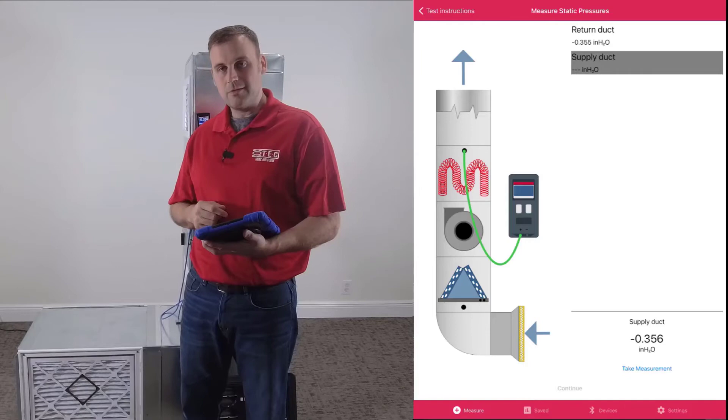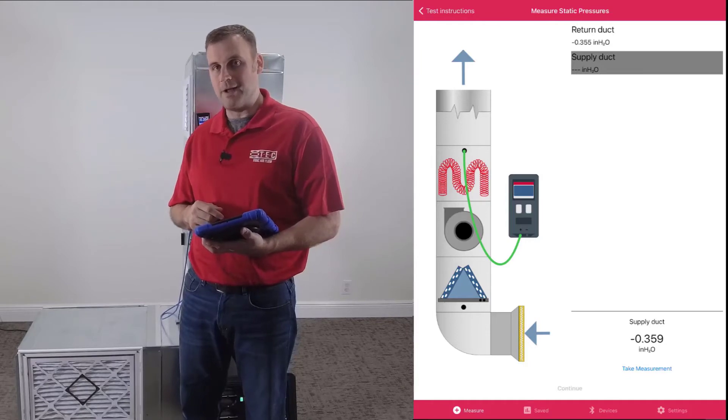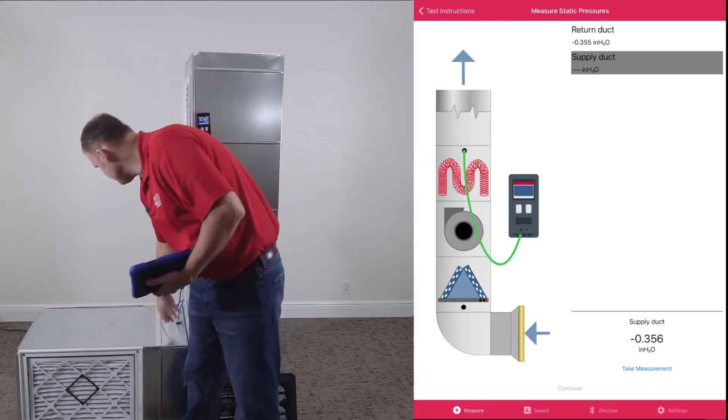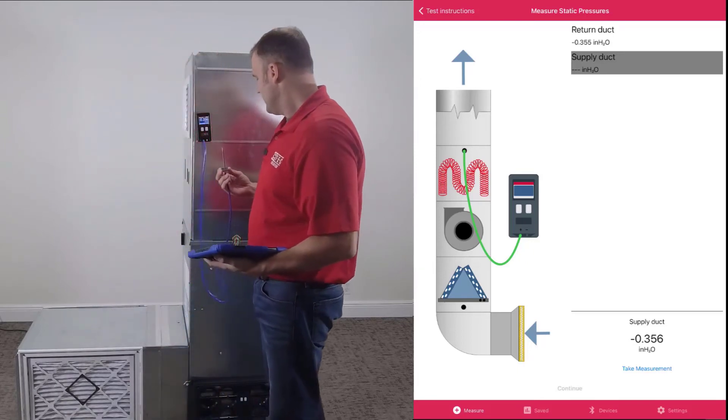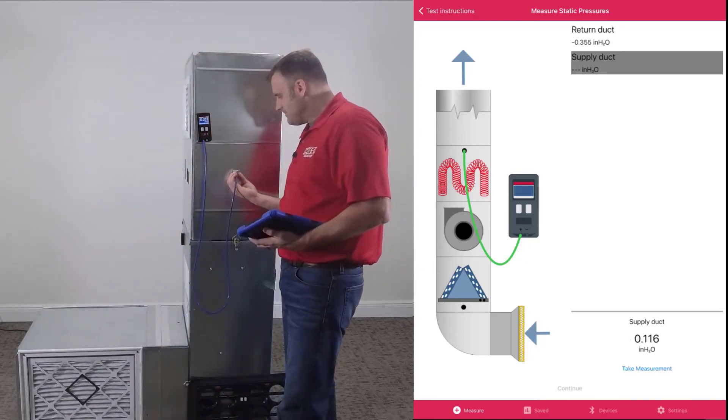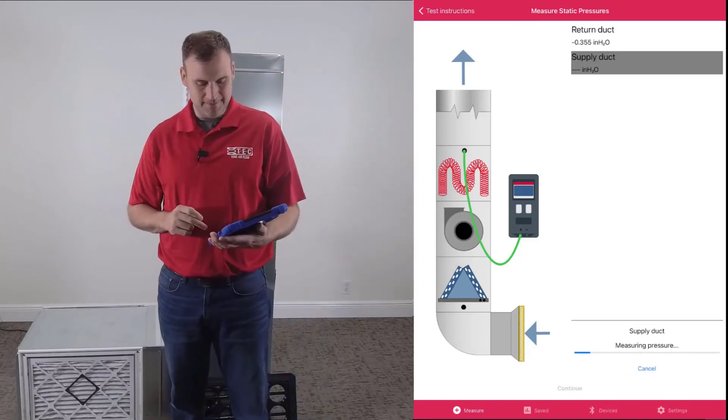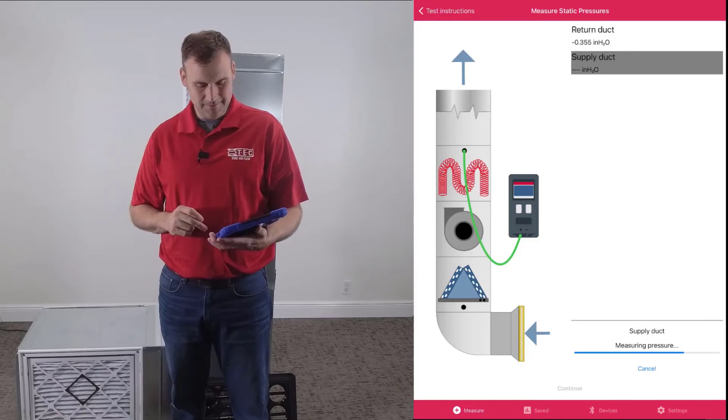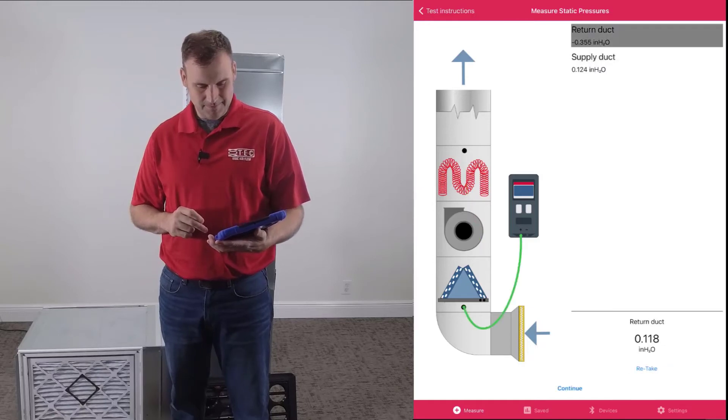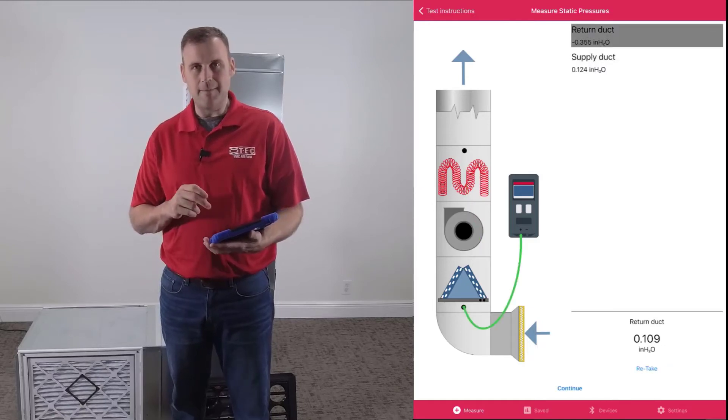Now you'll notice the screen is telling us let's go ahead and capture the supply static pressure measurement. Take that static pressure probe, put it in the supply plenum. We click take measurement, wait a few seconds. I'm happy with those measurements. Let's click continue.